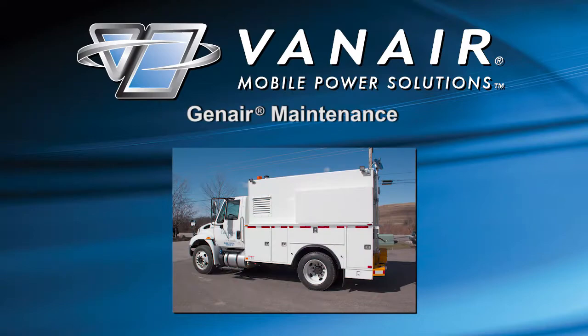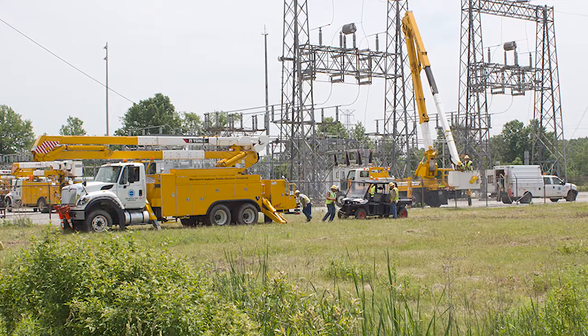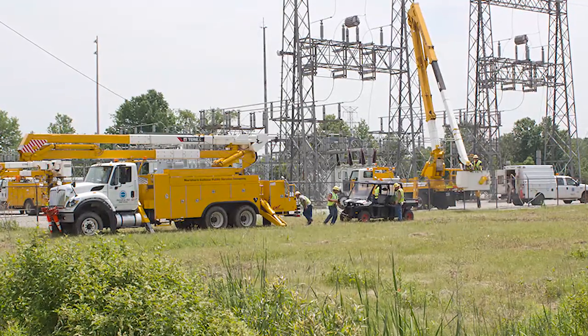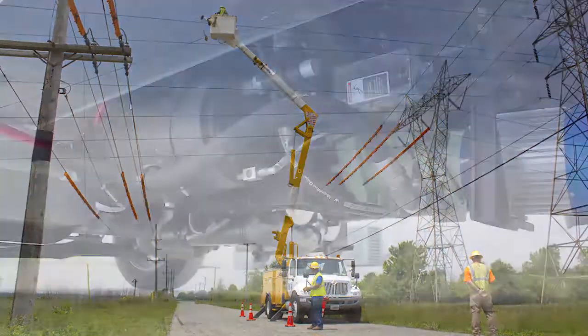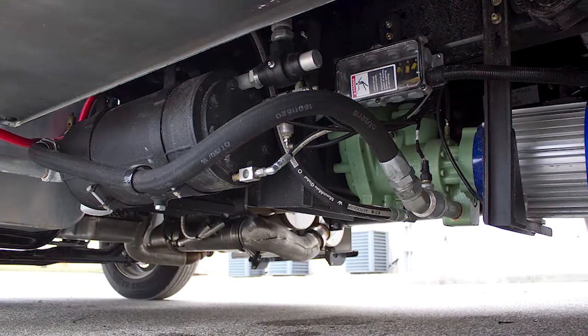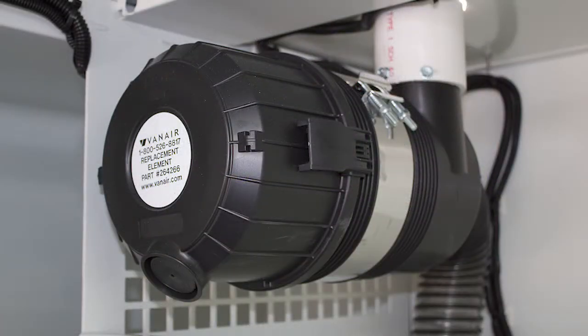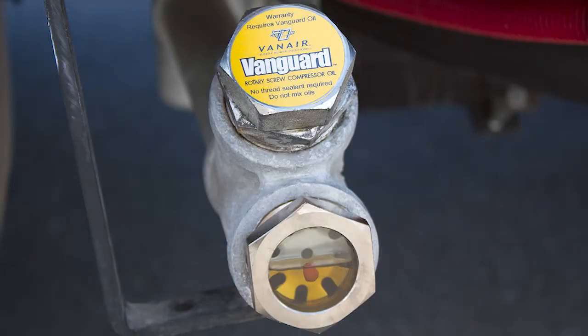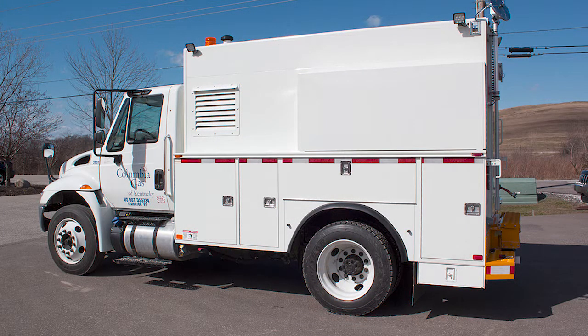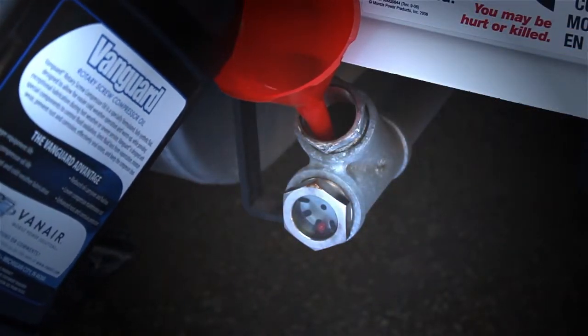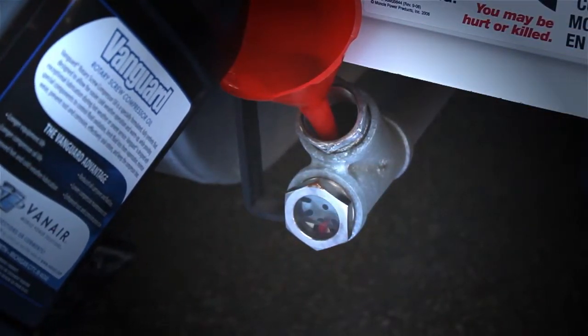The following maintenance or service intervals are required to keep the compressor and its components in good operating condition and to maintain the unit's warranty. Note that dirty operating conditions, as well as contamination in the compressor oil, will make it necessary to shorten these intervals. Take the time to inspect the air filter, oil level, and fluid condition during your standard vehicle pre-trip inspection. These simple steps should catch potential problems before they occur and prohibit many costly repairs.